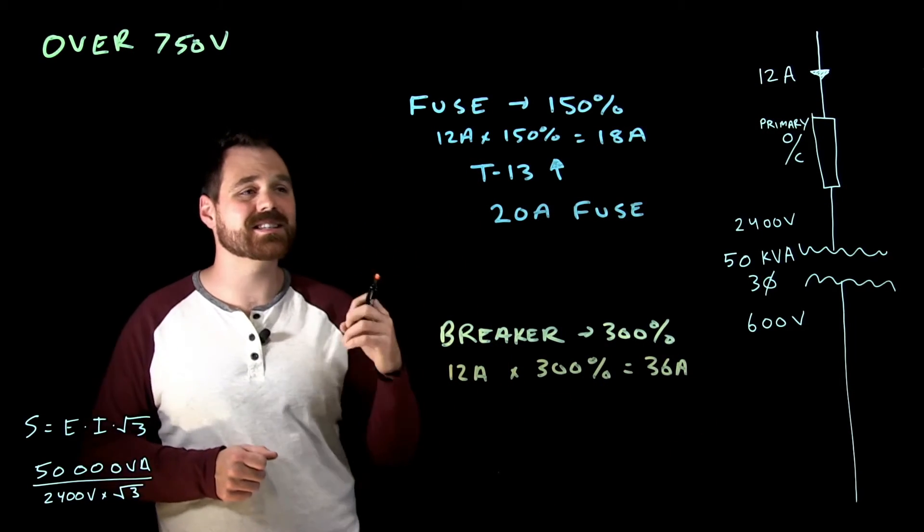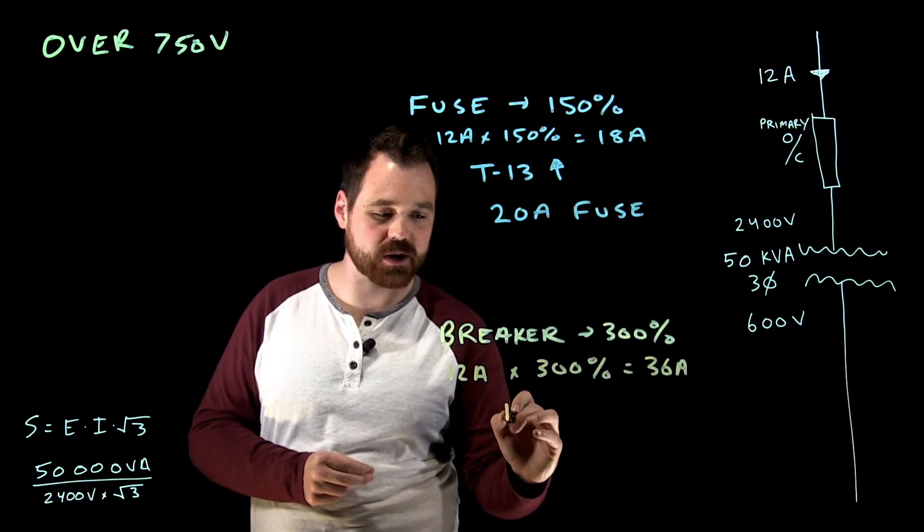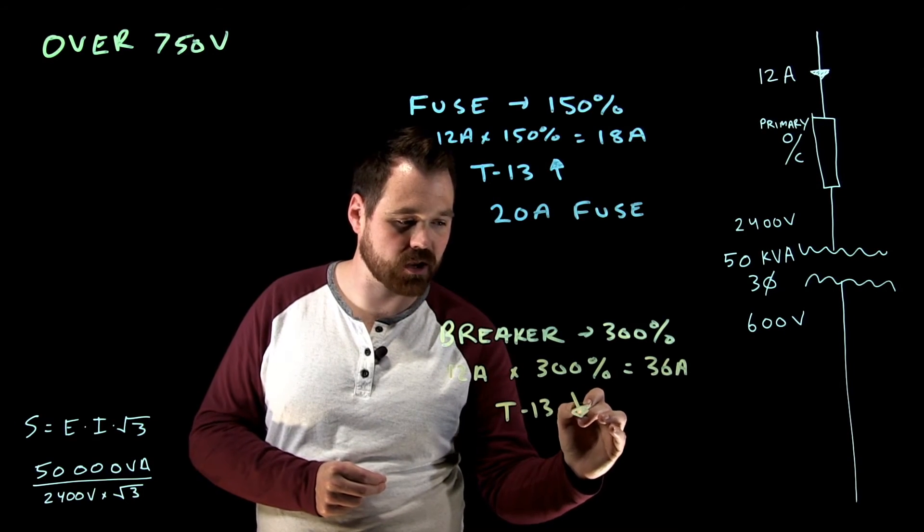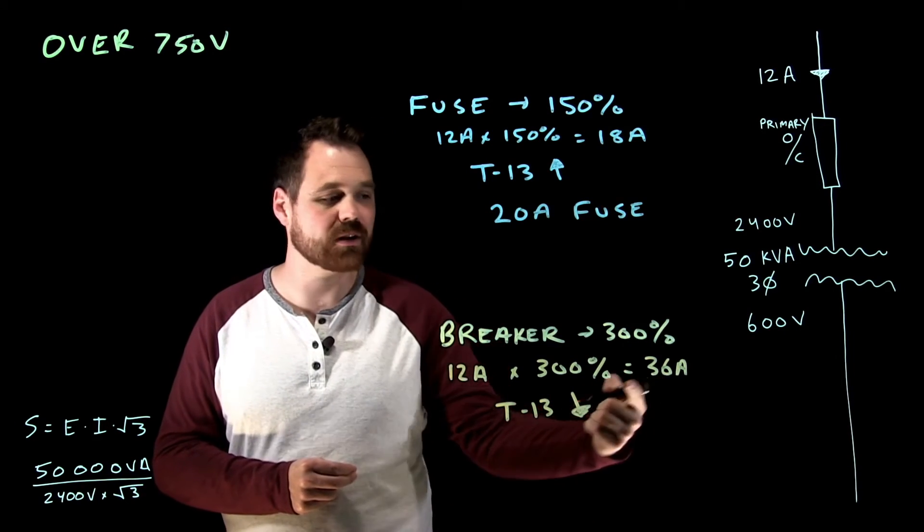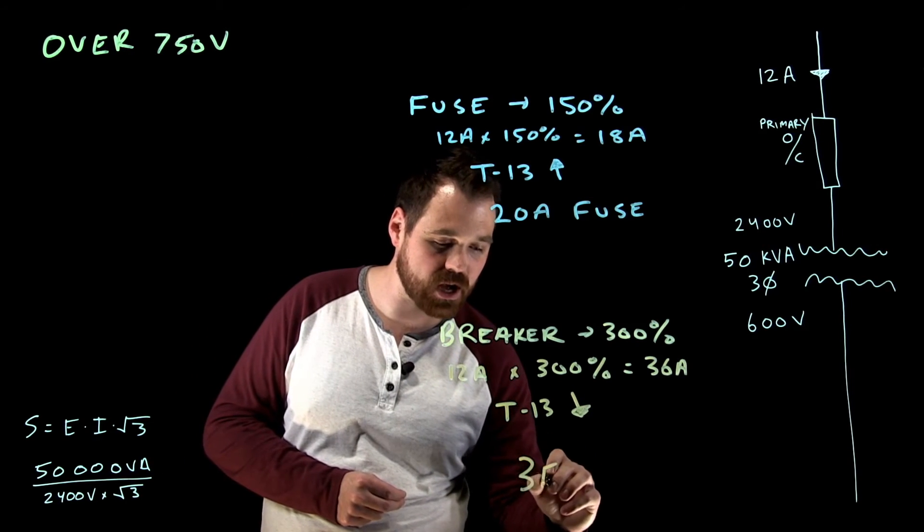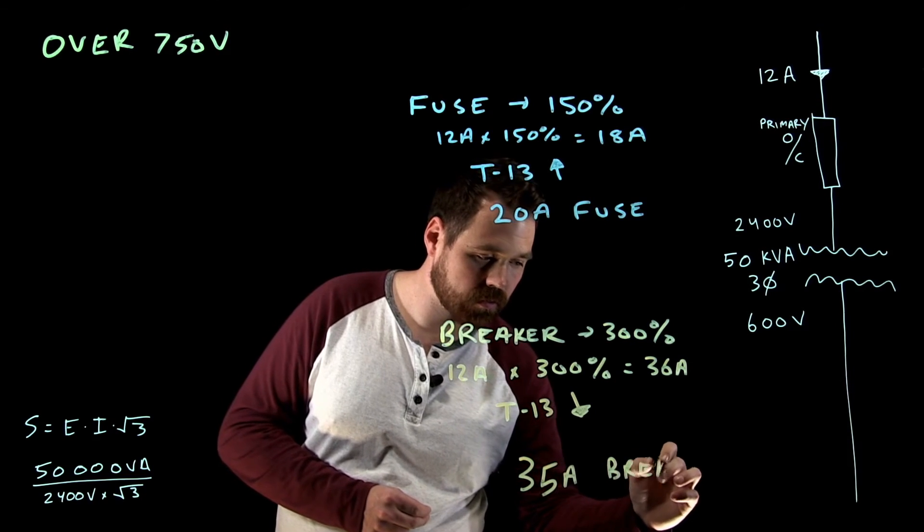Now in this case, it cannot exceed 300%. So that means when I go to table 13, I actually have to pick, if a 36 is not available, I have to go down to the next smaller size. So I'd end up with a 35 amp breaker.